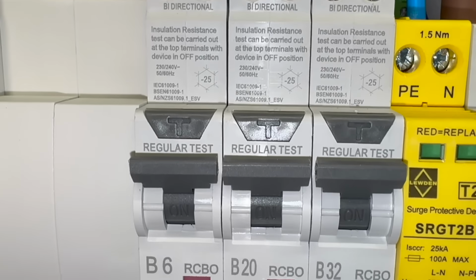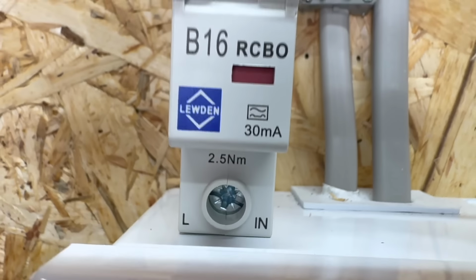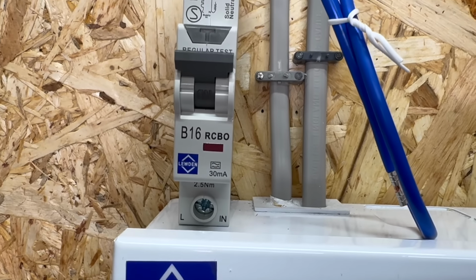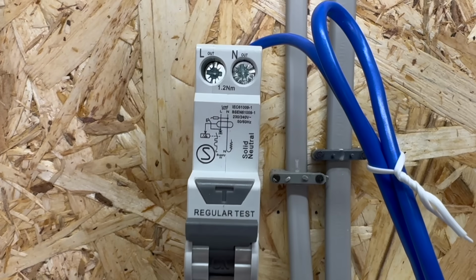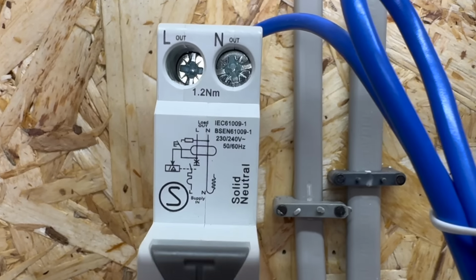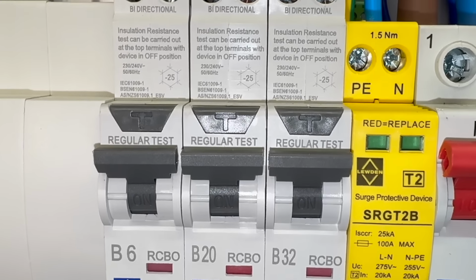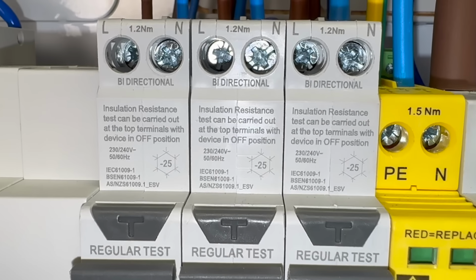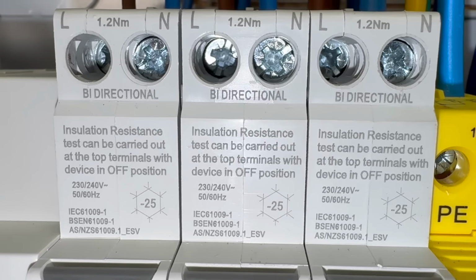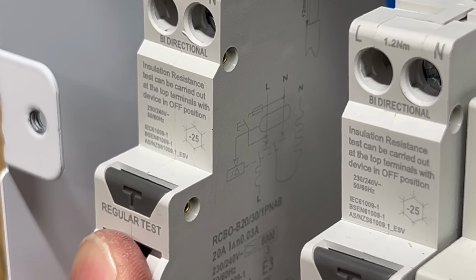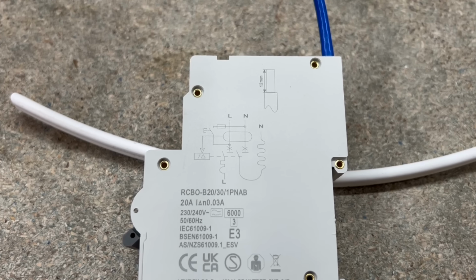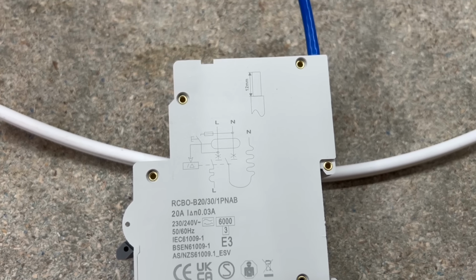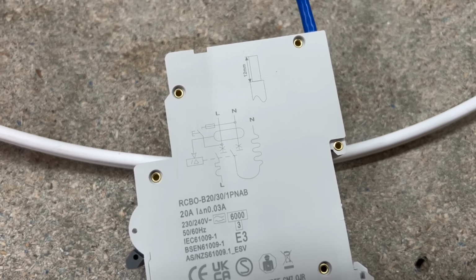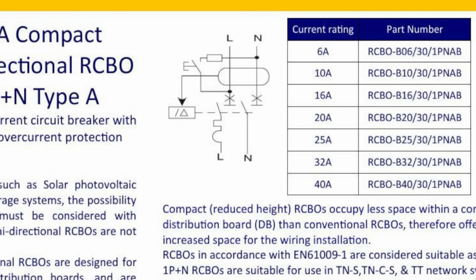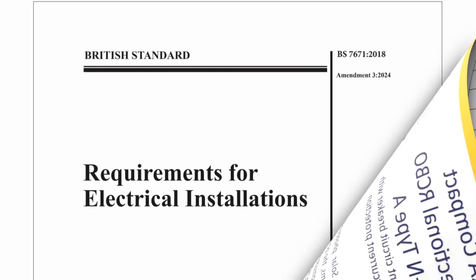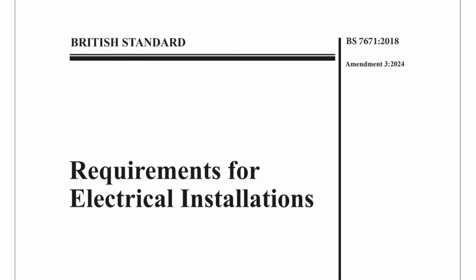Most RCBOs have marked terminals, line in, line out, and so forth, meaning they're unidirectional and must be connected correctly to work. If connected incorrectly and current flows backwards from a solar PV system, for instance, the device can become damaged. This is because the internal PCB and solenoid may remain energized after a fault, risking failure to trip on subsequent faults. The solution? Use a bidirectional RCBO with a mechanically linked contact that disconnects the PCB regardless of power direction. However, being double pole or neutral switching doesn't automatically make an RCBO bidirectional. Always check the datasheet. This issue prompted a rare urgent update to the 18th edition of BS 7671.